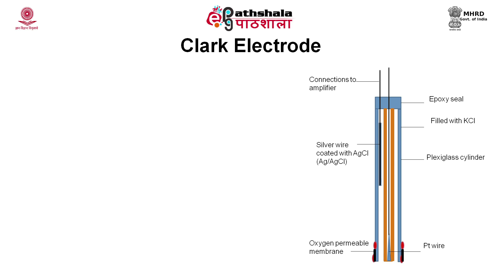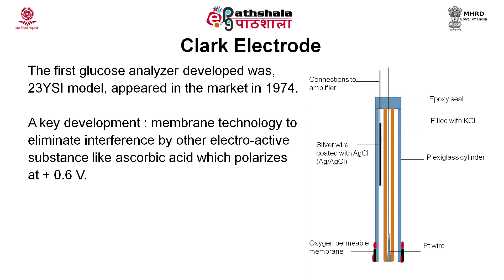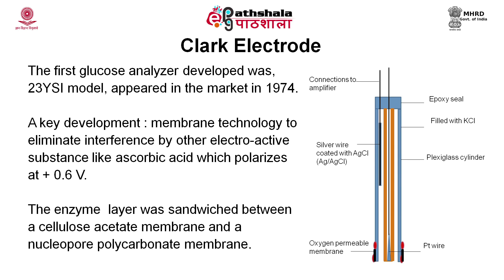This is the assembly of a Clark electrode, in which silver/silver chloride acts as the reference electrode, the platinum wire acted as the working electrode, and there is an oxygen permeable membrane. This kind of glucose analyzer was developed as a commercial product named the 23YSI and appeared on the market in 1974. The key development in this method was the use of membrane technology, which eliminated the interference of other electroactive substances like ascorbic acid, which also polarizes at 0.6 volt — the polarization potential of hydrogen peroxide. The enzyme layer was sandwiched between a cellulose acetate membrane and a nucleopore polycarbonate membrane.